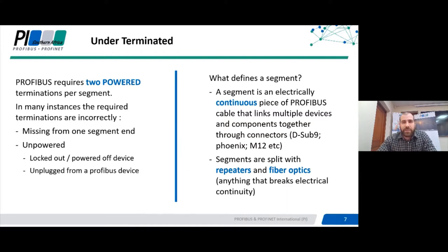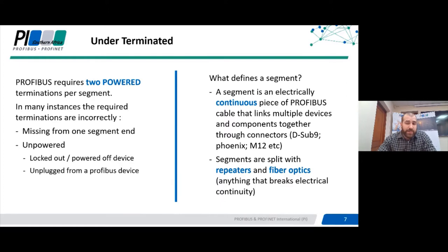The network is typically more at risk from other installation type faults as well. A quick and easy way to remember where termination should be enabled is typically where there is only one cable going into a connector. This isn't a hard and fast rule because of the dynamics of how your segment is designed and whether you're using stub lines, but generally where you have one cable going into a connector or device, that should be the end of the segment. An easy way to identify an under-terminated segment is to look at the signal quality of the bus telegram.